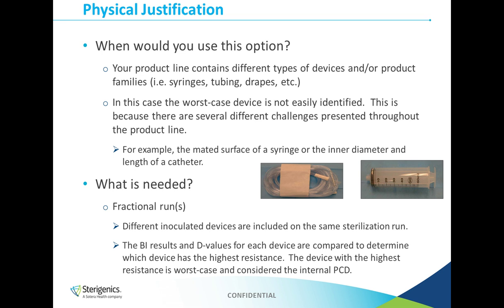So in this type of situation, you're going to have to go a step further and perform fractional runs. Now, on this sterilization run or this fractional run, you're going to include different inoculated devices. It's important that all these devices are included on the same run because you want to have them exposed to the same conditions. If you have them exposed to the same conditions, you can actually evaluate them against each other. If you don't have them on the same run and they see different parameters or different temperatures or different conditions, it's harder to justify that comparison.